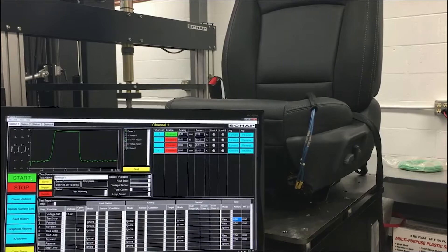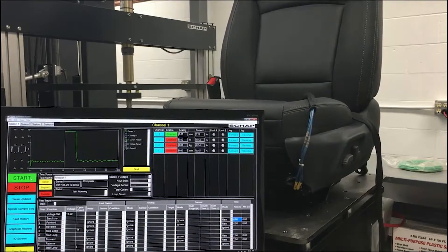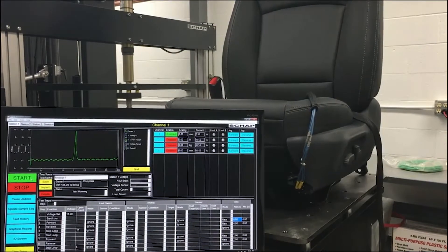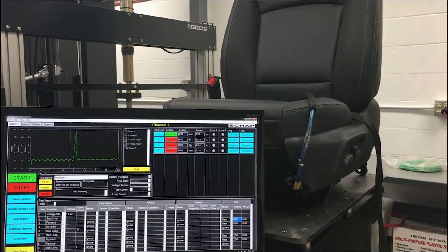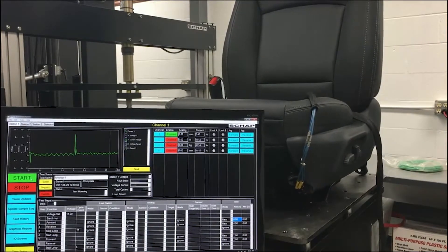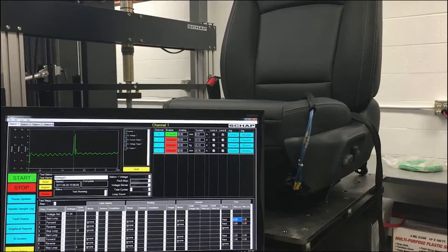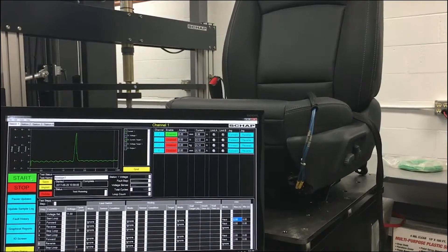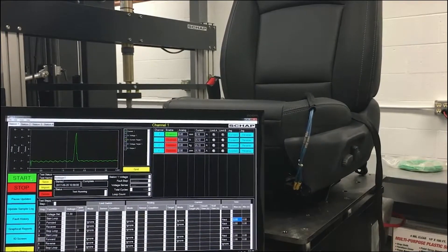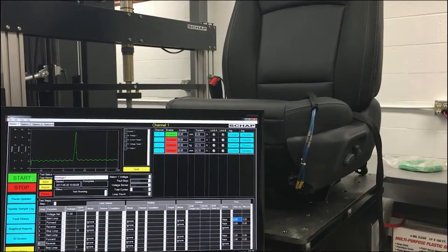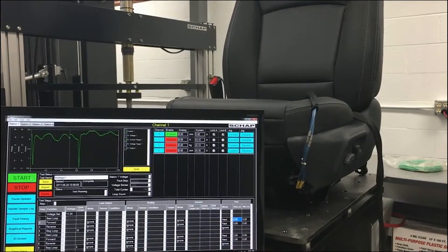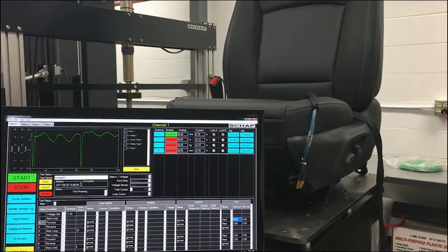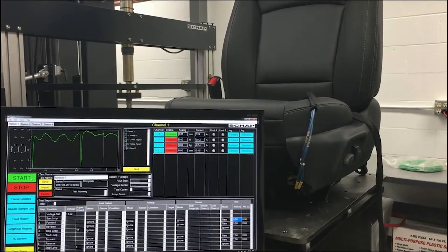The two parameters for the time limit condition are the maximum amount of seconds and the minimum amount of seconds. The maximum time in seconds is the time at which the condition will be triggered if the time mode is set to next. If the time mode is set to default, another condition (either limit, analog, or current) must be triggered before the max time is exceeded or the tester will generate a fault.